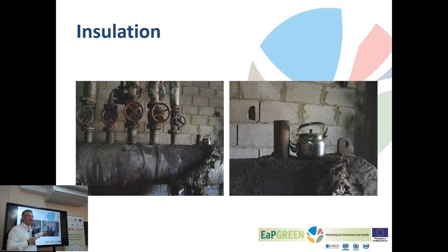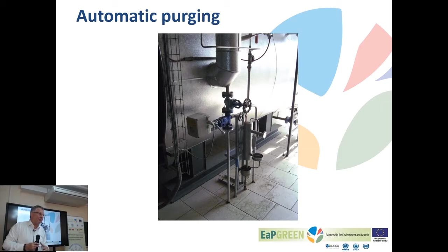Yeah, automatic purging, we are now getting into details, because in a steam boiler, every now and then we have to purge, because some hardness, some salts will accumulate in the hot water tank. Purging frequently is done manually. The operator every hour or so for 2-3 minutes blows down some hot water. The much more economic variant is to install a conductivity sensor and to have automatic purging, keeping the conductivity in the water at say 3,000, 4,000 microsiemens, and only discharging hot water when there is a build-up of salts in the boiler.